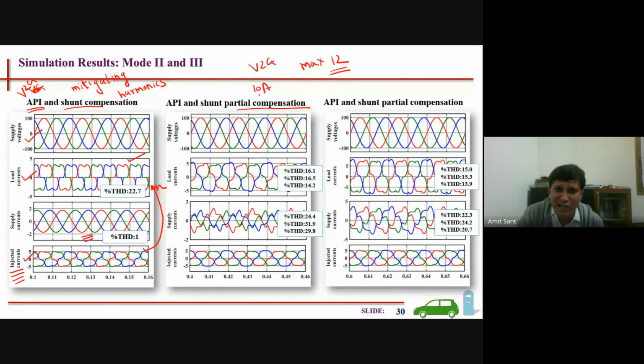So I can increase the peak value of current only by 2 amperes now. So what I will do, I will check if I go for fifth harmonic mitigation, is it exceeding the 12 ampere limit? No. Go for seventh also. Is it exceeding? No. Add 11th. Is it exceeding? Yes. Then stop. Only compensate for fifth and seventh. Don't go for 11th. Right?